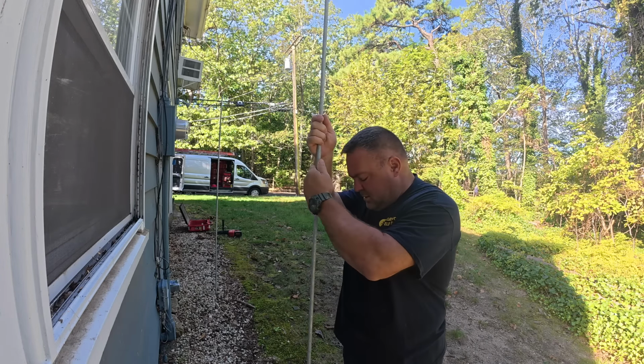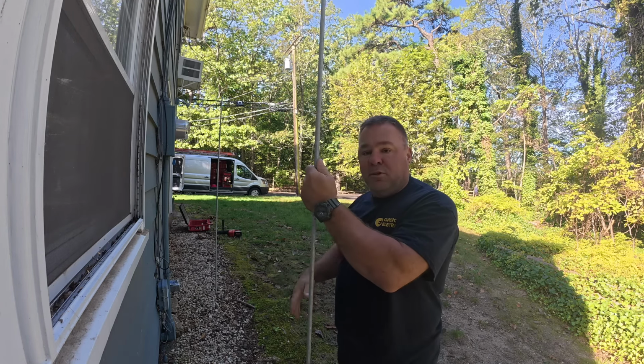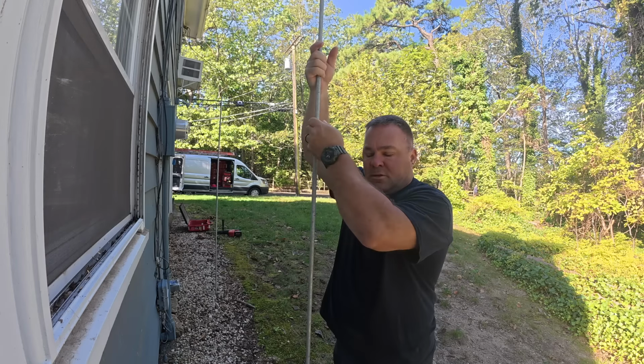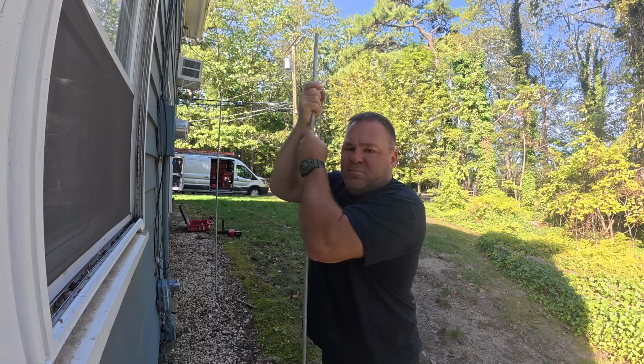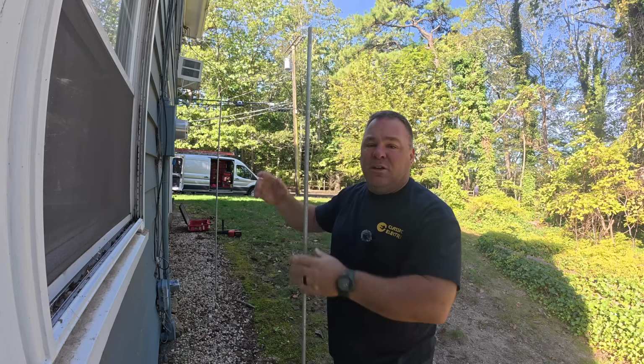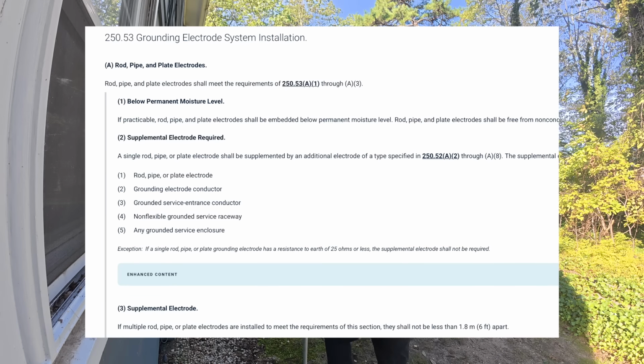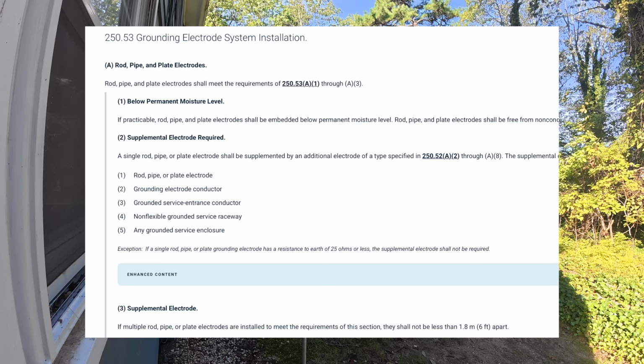Both of these ground rods have to be at least 6 feet apart from each other. I'll put the code section up on the screen as I'm editing this video. Both ground rods are installed 6 feet apart as required by section 250.53(A)(3), which is that last sentence at the bottom of this paragraph here. Must be spaced 6 feet apart.